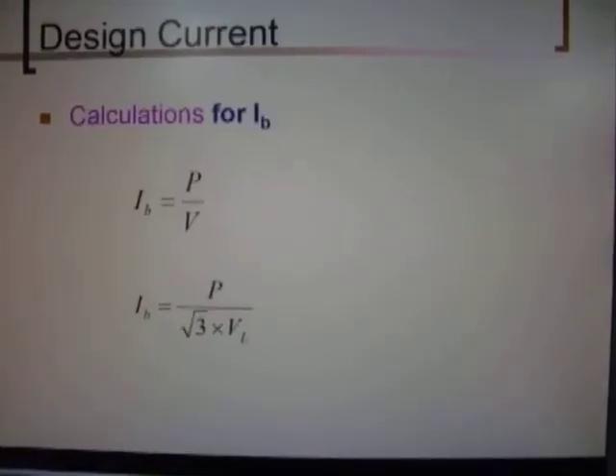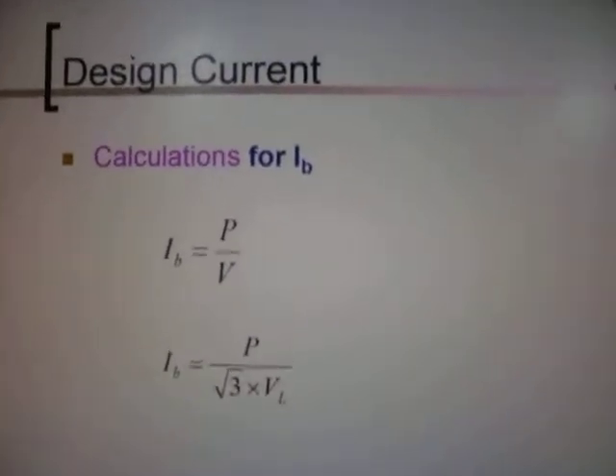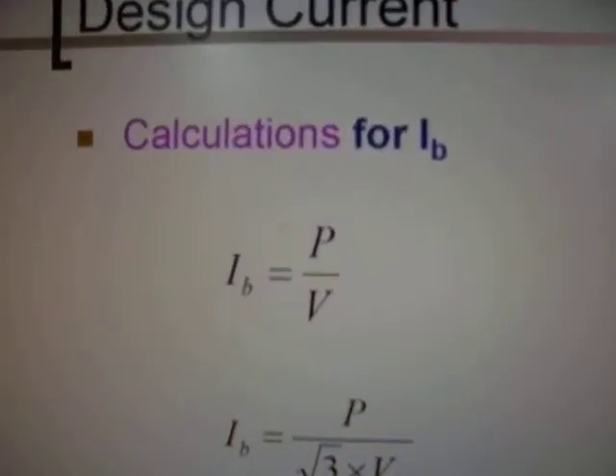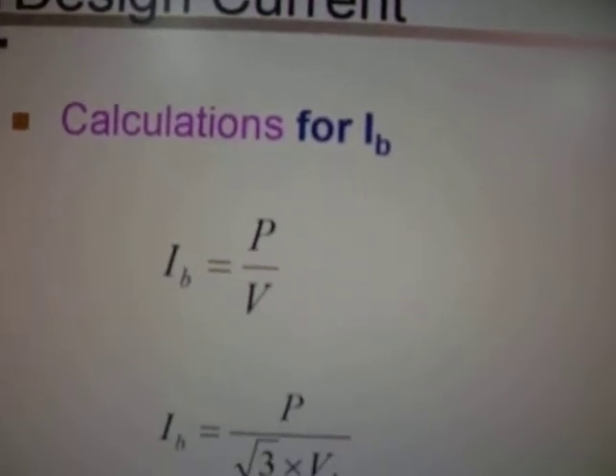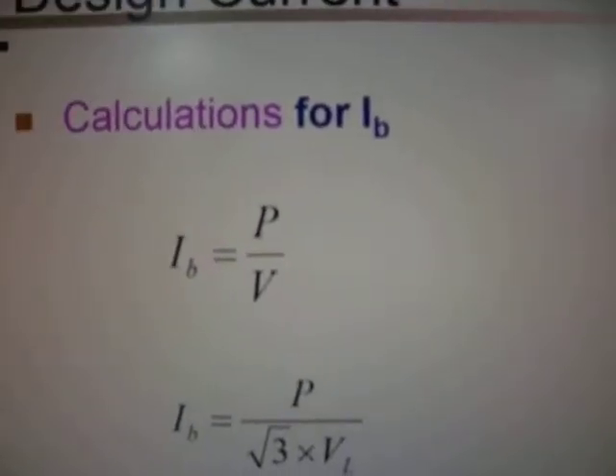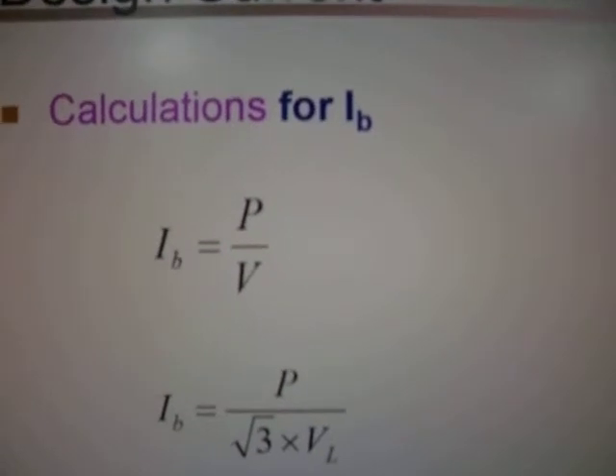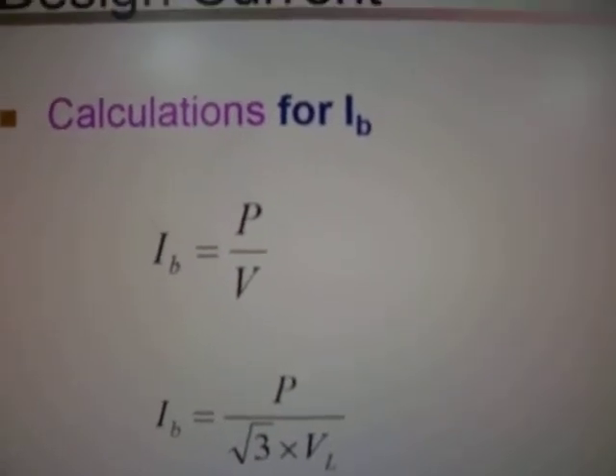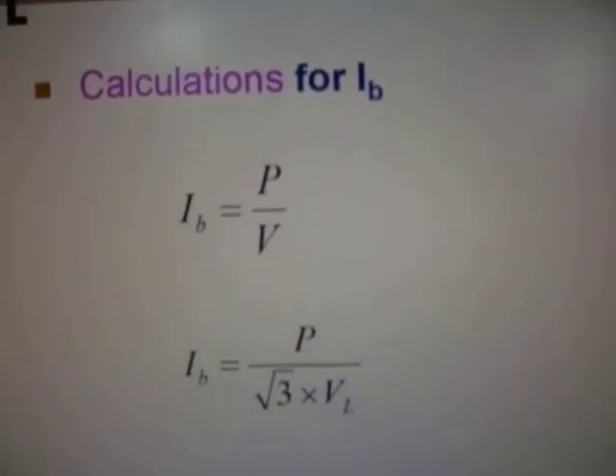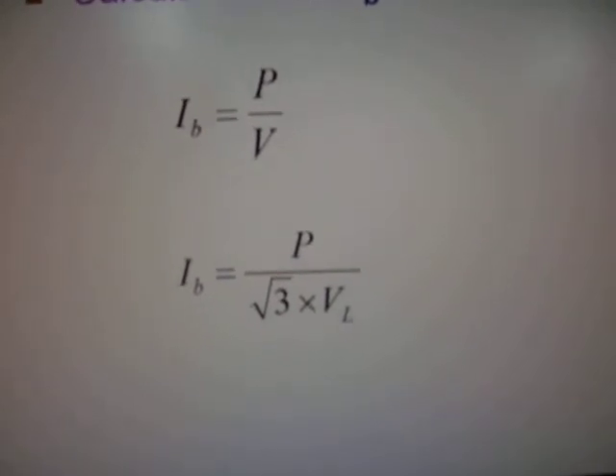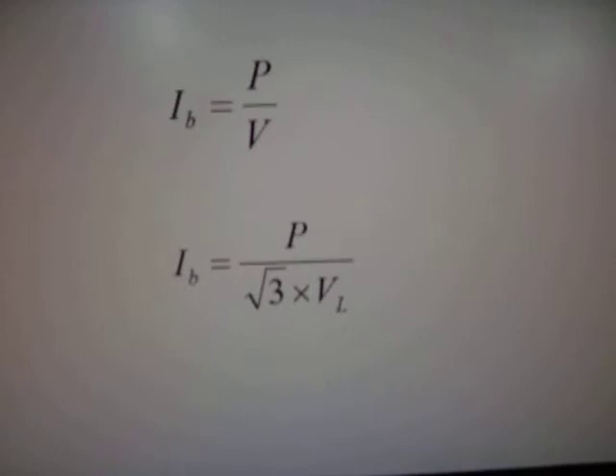Now here we look at the design current. Here we have the calculation for IB: IB equals P over V, where P is the power and V is voltage. And down here we have IB equals P over the square root of 3 times V.